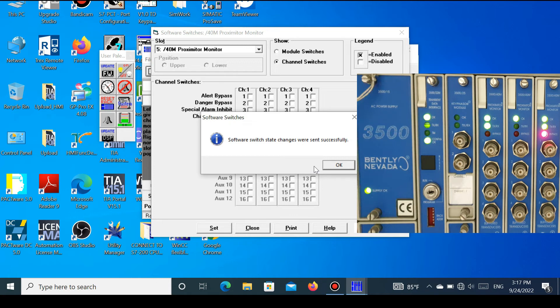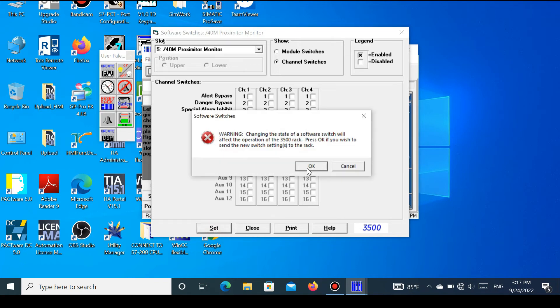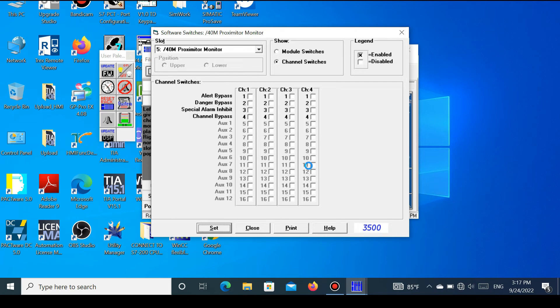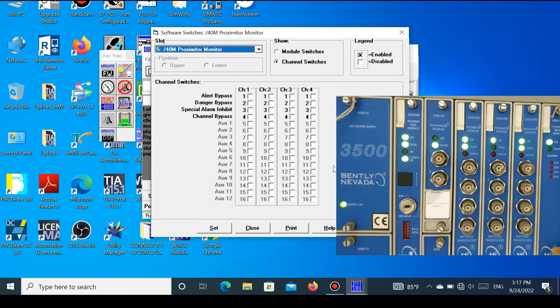If you see this bypass alarm in the status, it means the channel was bypassed. To remove the bypass, uncheck and press Set, then press OK. The vibration channel bypass is removed successfully, and the status shows no bypass alarm, confirming the bypass has been removed.